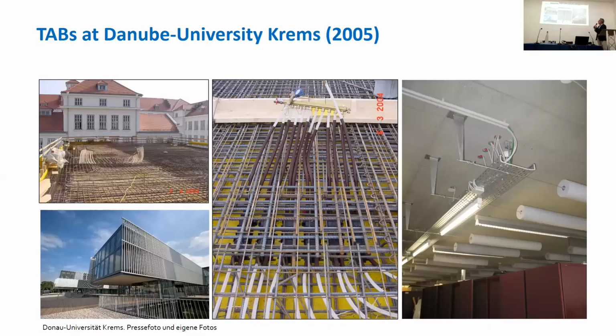And the building physicists decided only after finalization of the building that they had an acoustic problem and came up with these wonderful acoustic measures. And these wonderful acoustic measures have been mounted with long steel drills. And for sure, on 10 places, they demolished the pipes. And there I learned that you cannot repair it. And as a strong measure, it was in my own office. So I lived then without cooling in this place.